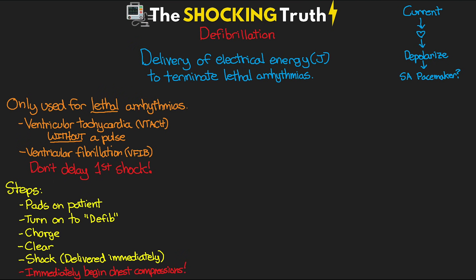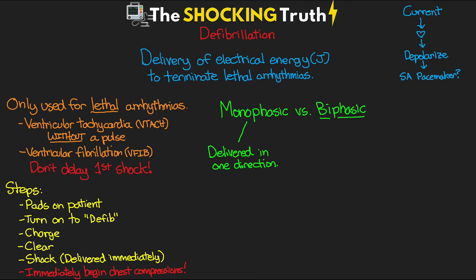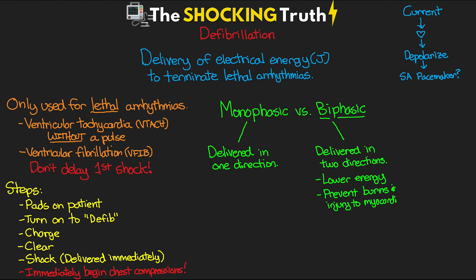You may have heard about the differences between monophasic and biphasic defibrillators. Most hospitals today are using biphasic devices. Monophasic devices — now considered old technology — delivered electricity in one direction between the pads. The biphasic device delivers the electricity one way, then switches directions and goes the other way. This biphasic delivery allows for lower energy requirements, which primarily helps prevent burns and injury to the myocardium. Studies have shown that using the biphasic approach delivers a higher chance of first shock success.